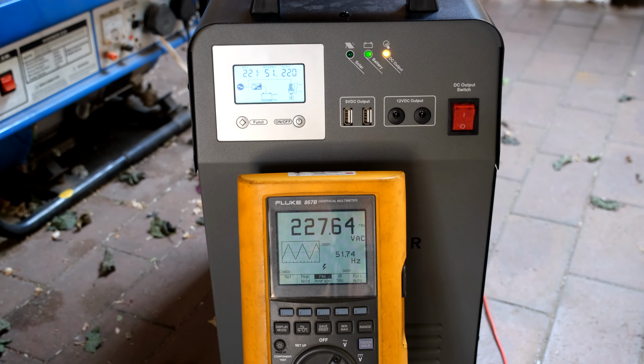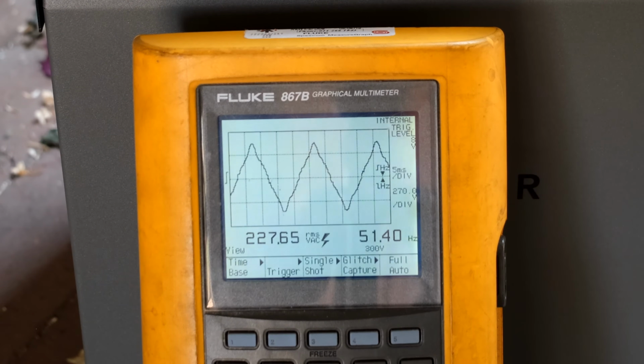So will the inverter offer you clean power? Well, no, not if it is in the bypass or the normal mode. So if it's running off the mains, no. If it is running off the battery, yes. Right, so there's a closer view of that waveform, and what I'm going to do is load up the generator. The reason is that these types of generators, when they get loaded, their voltage and frequency tend to drift. So I'm now loading the generator, and watch what happens to that waveform and the frequency.